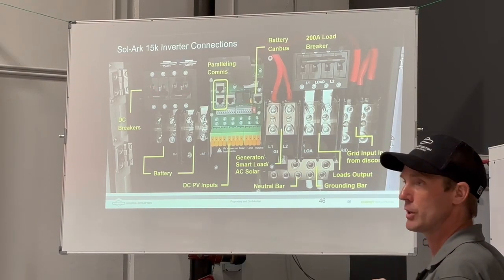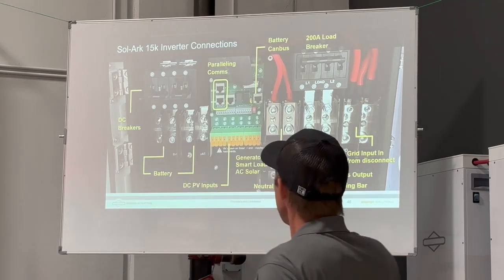On the left side of the 15K is the DC side. The DC busing is right above this. There are two independent 200 amp breakers here for the two independent inputs. Both of these breakers are on the positive battery terminals. So we've got two positive battery terminals, and battery 1 positive is interrupted here, and battery 2 positive is interrupted there. You only need a single pole breaker for DC, right? You only have to interrupt one part of the loop. But they're combined right after this breaker. Those two bus bars become a common DC bus inside the inverter.